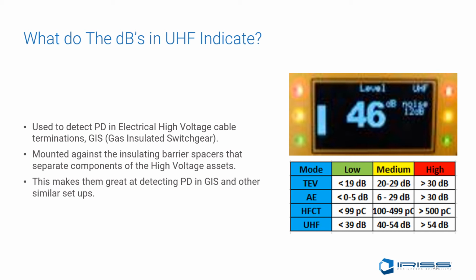UHF testing is effective at detecting PD in GIS and other similar setups, so for on-site PD detection, the ultra-high frequency mode has been employed in the field and showed its effectiveness as a detection technique. The main advantage of the UHF method is its immunity to external electromagnetic interference with a high signal-to-noise ratio, which is necessary for on-site monitoring. Considering the detection process, sensors play a critical role in capturing signals from PD sources and transmitting them into the UHF sensors.